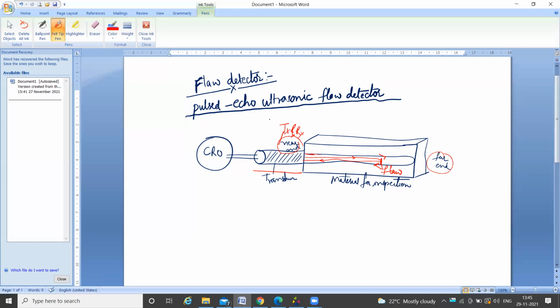That's why this particular ultrasonic wave is reflected back in less time. Therefore, the pulsed echo method currently in use is very sensitive, since echo pulses of energy as small as 1% of the total transmitted energy are sufficient for recording the echo. If there is an echo, it represents the flaw in the material.